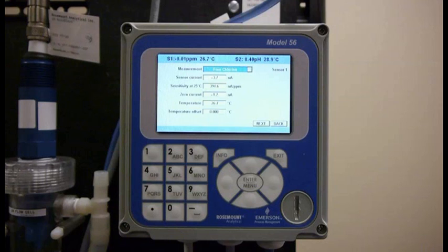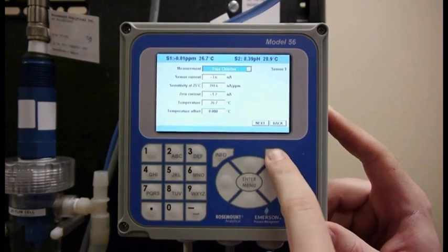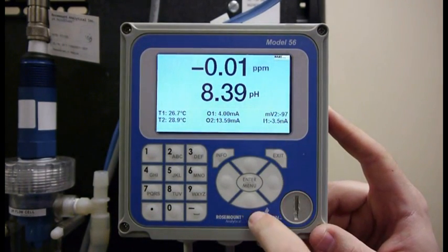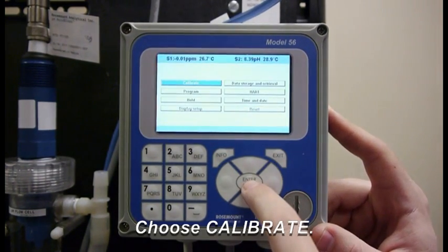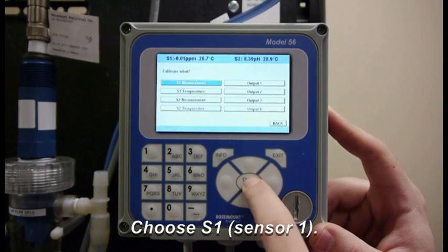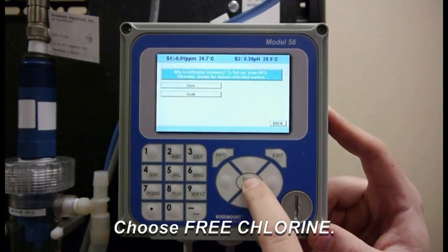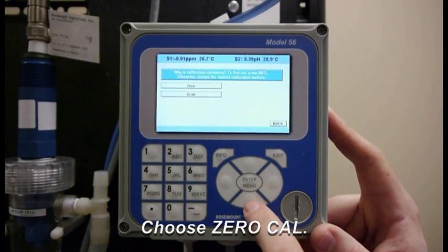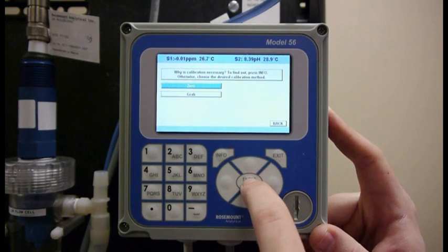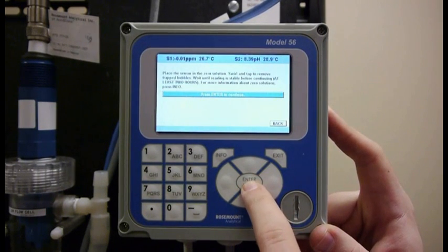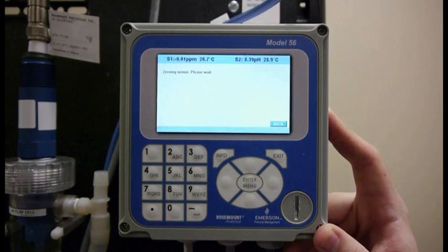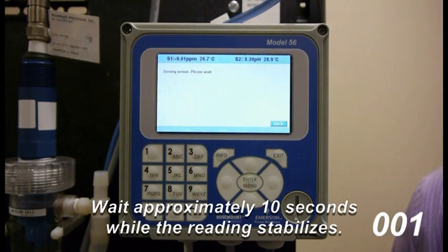So I go on to the next step where I'm going to actually zero the sensor. I'm going to exit. Now I'm going to go to Enter for the menu. I'm going to go to Calibrate. And I'm going to do sensor 1 as it's our free chlorine sensor. And I want to do a 0 sample. Here I am going to hit enter for the 0 calibration, and it's going to tell me to wait for, I don't know, about 10 seconds.